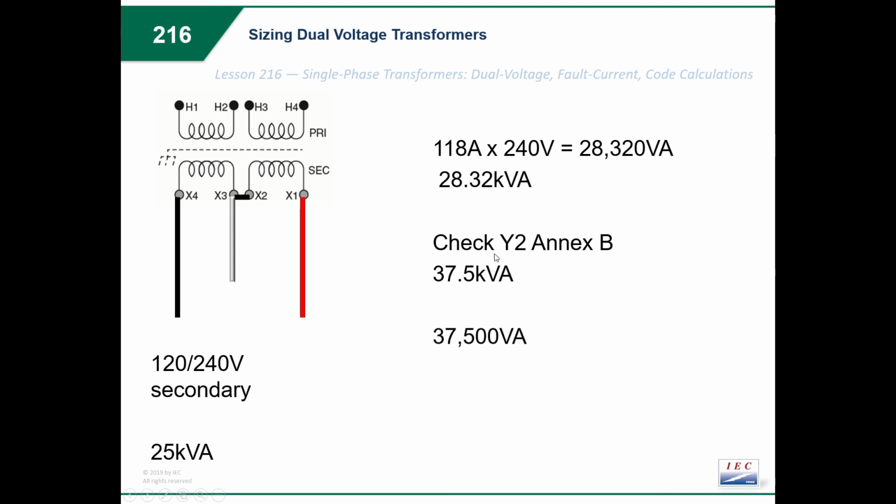So let's first go from kVA back to VA. We're going to divide by 240. That tells us 156.25 amps on either phase. So we've given this guy a little bit of spare capacity now. Rather than just 118 amps, he's now 156. That's pretty much the range where we want to be. So again, I think that's a nice little exercise.